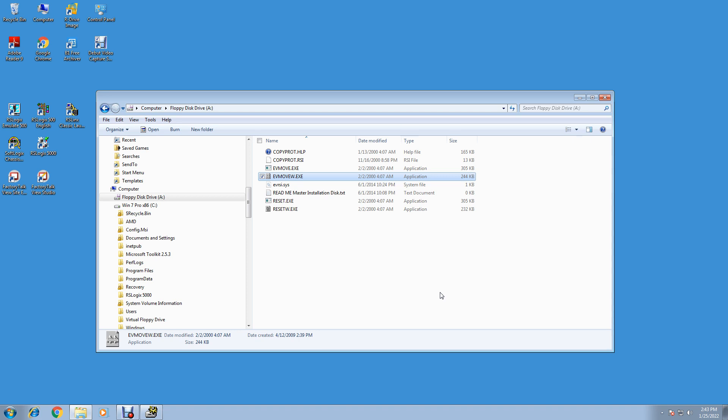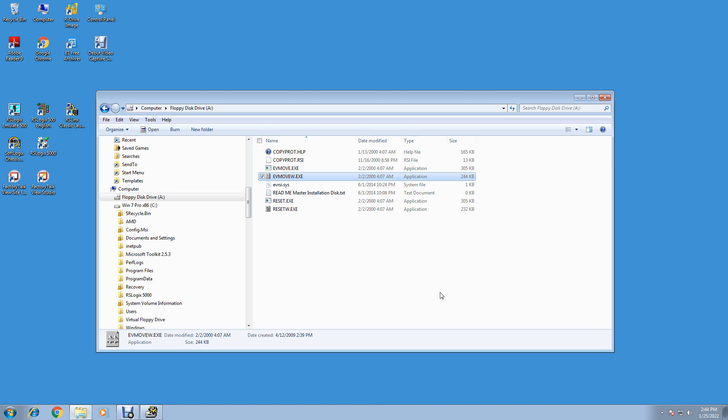RSLinx, the communication software, will run in grace period for seven days without it, but the SoftLogix PLC will not start up unless it finds an activation file. It'll just say startup and say activation not found and shut back down. So you have to have your activation files in first before you install your software. We're good to go. We got our activation.